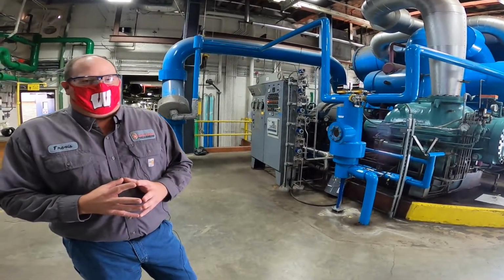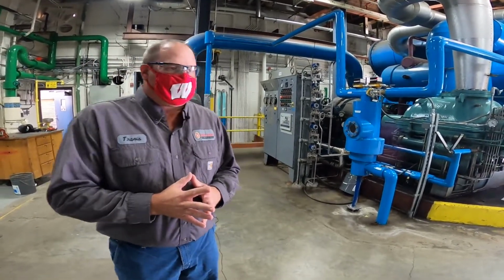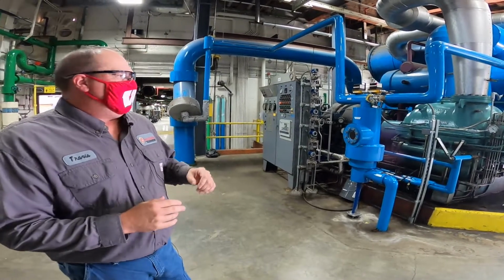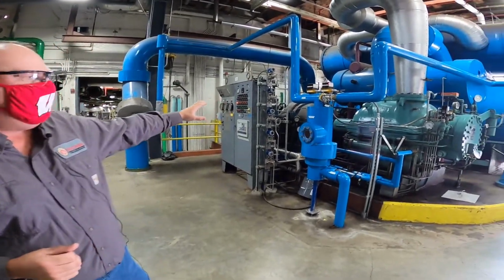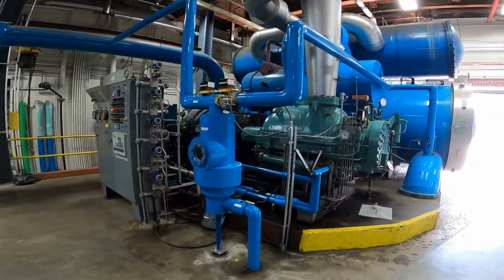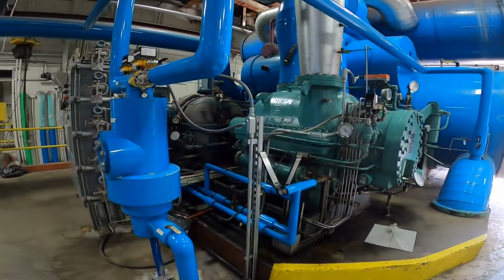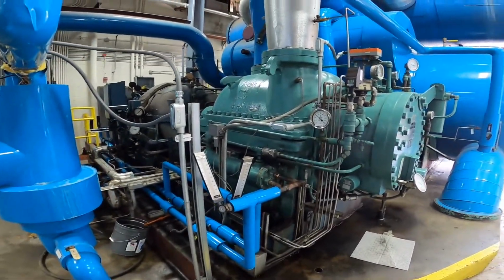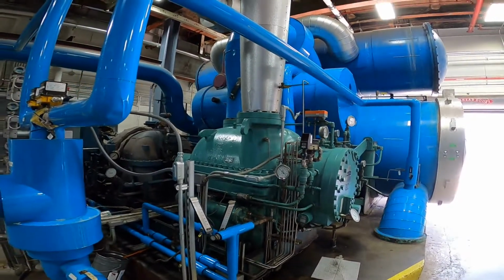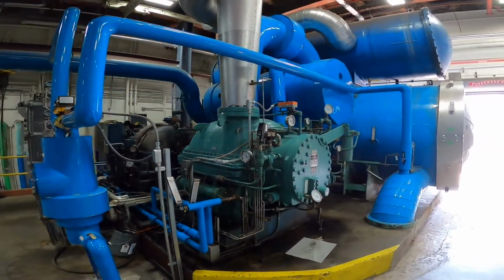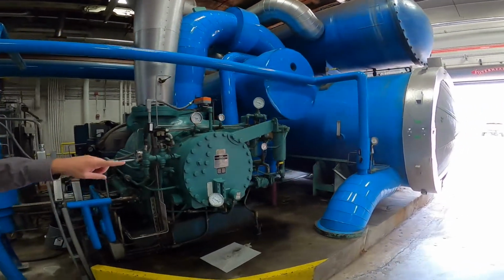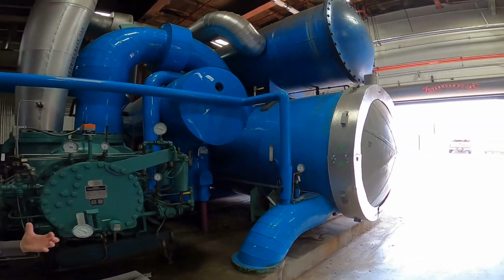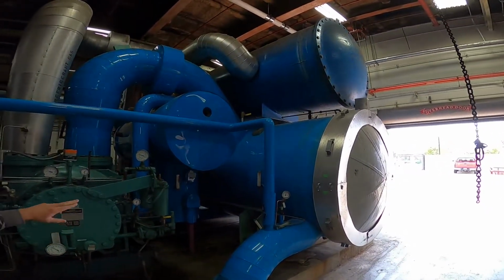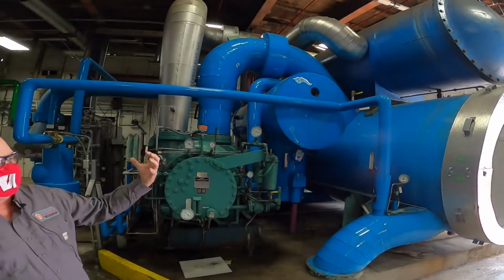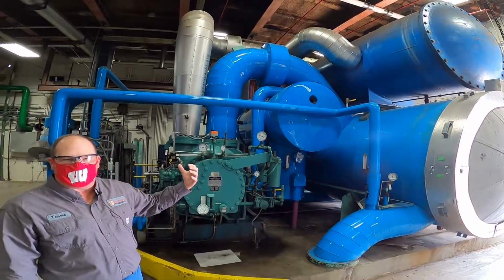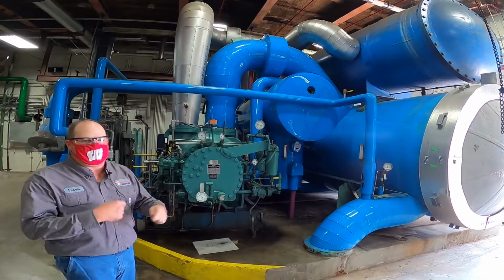Just to recap, you need to make steam to run the motors that drive these chillers. Yeah. As you can see on the one end, we have a steam turbine, which drives the compressor of the chiller, and that compressor is what drives the Freon gas in the Freon cycle up through the condenser, and it pulls the Freon from the evaporator in a continuous, closed loop. The chill water from campus travels through the evaporator, so the water coming back is about 50 degrees Fahrenheit. When it passes through, the Freon picks up the heat, and we control that to about 40 degrees on the chill water supply to campus, and it's a continuous loop.